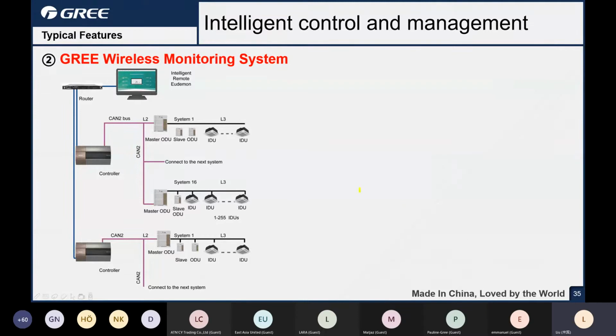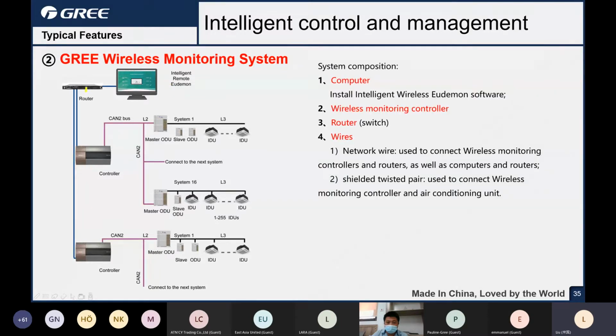And if we have a look at the detail, now you can see this is the topology network of the intelligent monitoring system. For this software, first you need a computer, right? You need a computer and a router to plug your cable, and also a controller. This is a gateway, the monitoring gateway. Each gateway connects with the router, and then each gateway connects with your VRF outdoor unit. Then all of the system parameters, running parameters, and error information can be transmitted to the controller, and the router can collect them and send them to the computer, and finally you can get the display on your laptop.